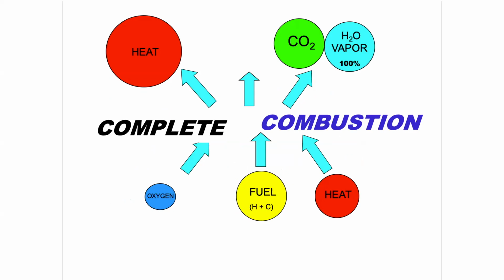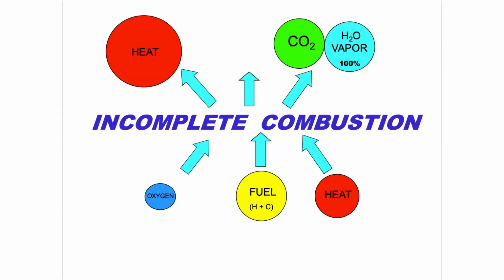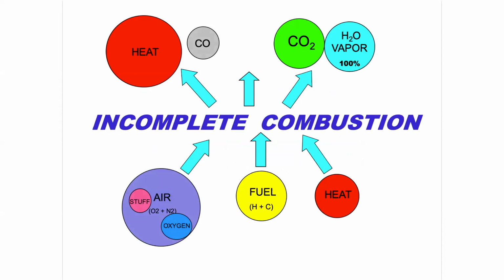So going back to this illustration where we left it a minute ago with undiluted combustion, perfect combustion, let's look at what we call more complete combustion. Look at more of the elements that are actually happening here, get a little bit more refined, or even incomplete combustion when things don't go correctly. So air, now we've expanded the definition of air in our little simple diagram to have about 1/5 of it be oxygen, most of it be nitrogen, and other things that could be entrained in the air. These are things like hydrocarbon vapors, cleaning solutions, things like that that could also be in the air.